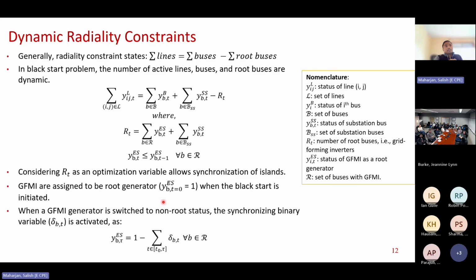Okay, so the next thing is the radiality constraint. The radiality constraint generally says that the number of lines should be equal to the number of buses minus the number of root buses. The root buses in our case are defined by grid forming inverters, right? But to allow the synchronization, some of the grid forming inverters have to give up their root bus status, right?